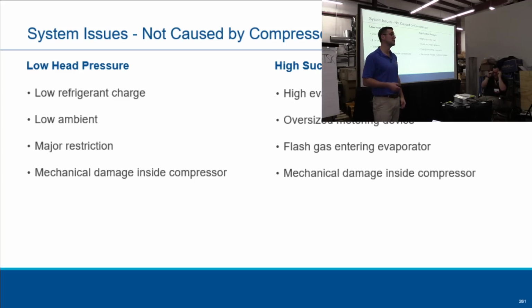I get this sometimes too. A contractor gets one, goes to install it, and says it's DOA, dead on arrival, they call it. Don, what do we do for every one of our compressors before they leave our factory? We test run them, and when they come back under warranty, we test run them. I'm not going to get into the pie charts, but 30% of the scroll compressors that come back, they run. And we classify that as NFF, no failure found.